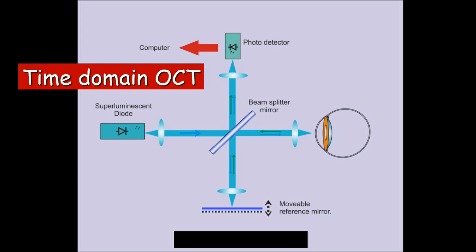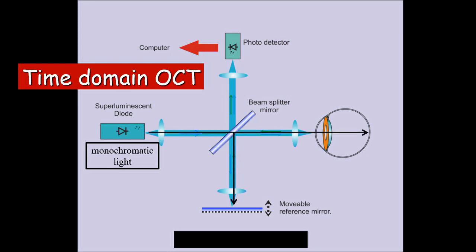In time domain OCT, a monochromatic diode light reaches a beam splitter. Half of the light goes into the eye and the second half goes into a mirror. Light comes back from both paths, they interfere together, and the combined signal reaches a detector.